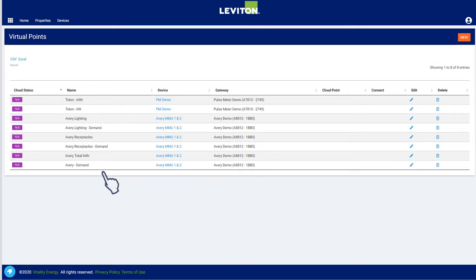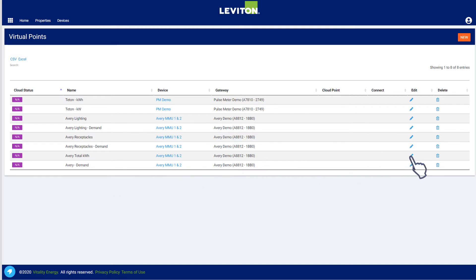Virtual points are an easy way to address code compliance requirements. One of the primary requirements of the energy codes is the disaggregation of load types. Lighting loads, HVAC loads, plug loads, and overall total load can all be calculated using virtual points. These virtual points can then be displayed on the dashboard and used in reports.